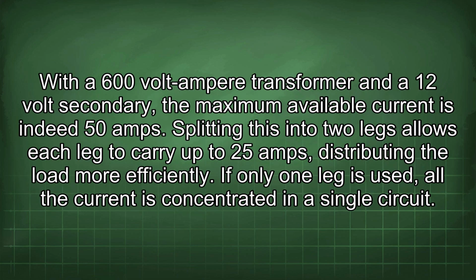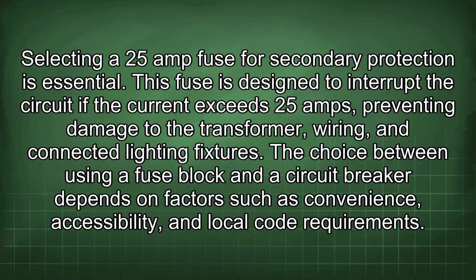With a 600-volt ampere transformer and a 12-volt secondary, the maximum available current is indeed 50 amps. Splitting this into 2 legs allows each leg to carry up to 25 amps, distributing the load more efficiently. If only one leg is used, all the current is concentrated in a single circuit. Selecting a 25 amp fuse for secondary protection is essential.